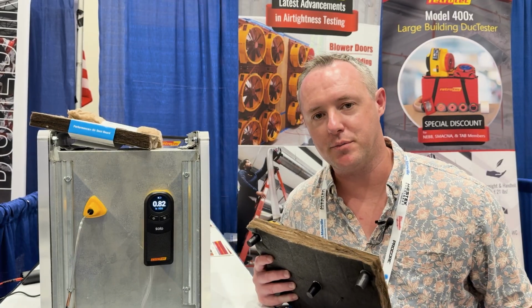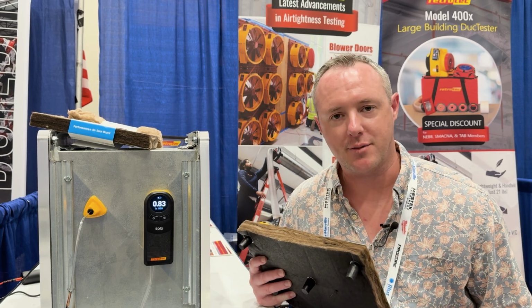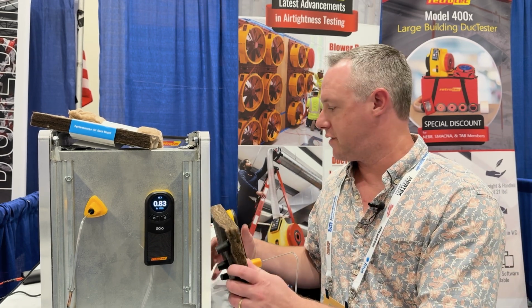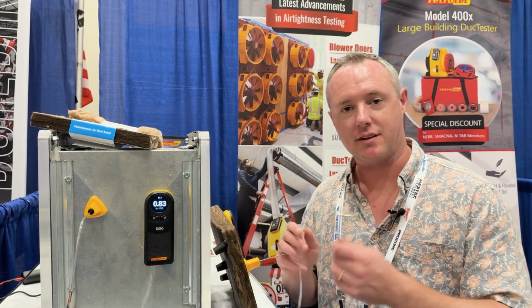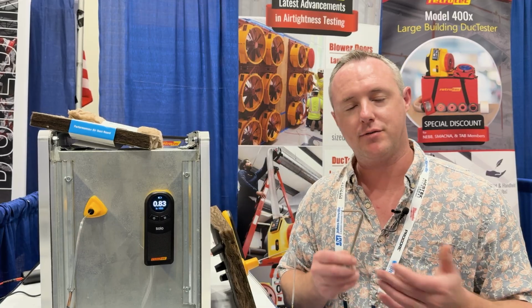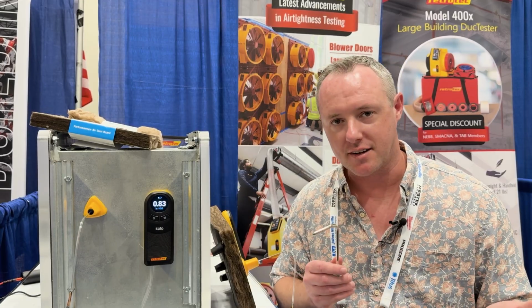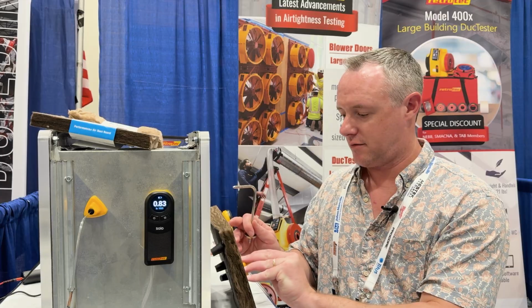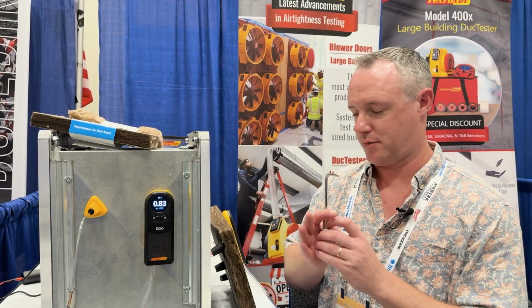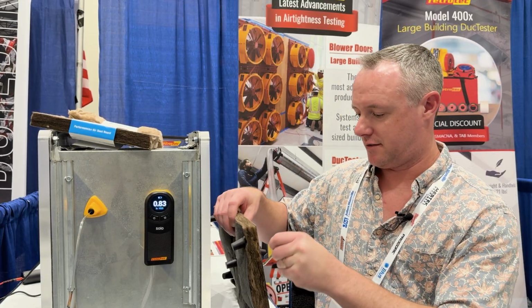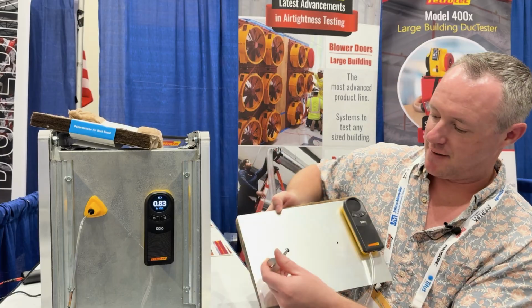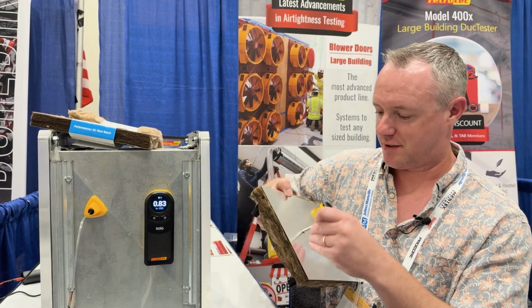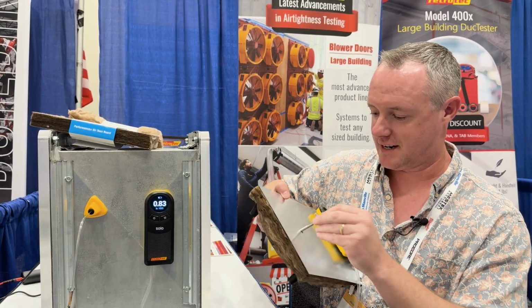Let's talk about the shape of the probe. Traditional static pressure probes have more of an L shape to it, something like this. What we've learned is that it's really not necessary. In some cases, if you use a probe like this and put it into the ductwork, even if you have the right size hole for this probe, sometimes it can be a little finicky to get it in there.